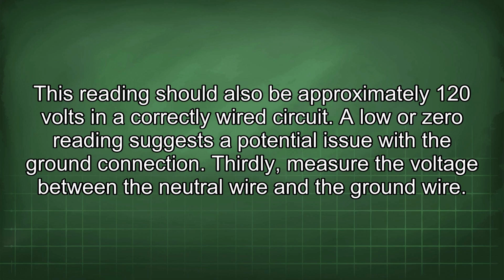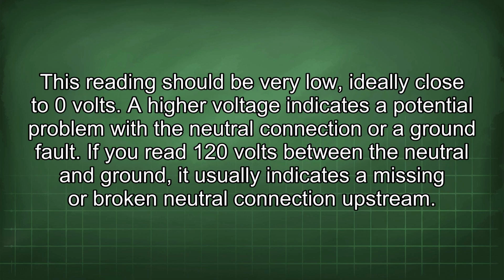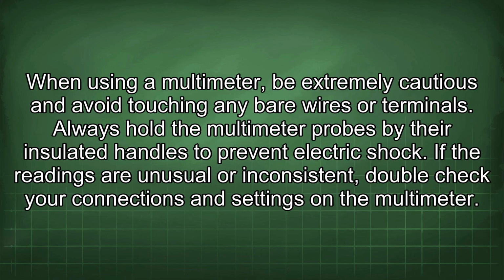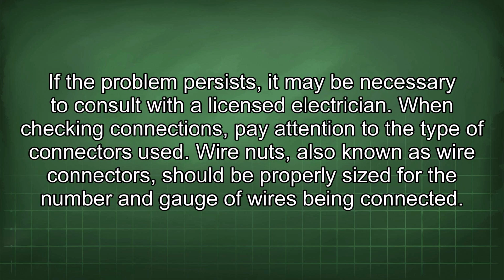Thirdly, measure the voltage between the neutral wire and the ground wire. This reading should be very low, ideally close to 0 volts. A higher voltage indicates a potential problem with the neutral connection or a ground fault. If you read 120 volts between the neutral and ground, it usually indicates a missing or broken neutral connection upstream. When using a multimeter, be extremely cautious and avoid touching any bare wires or terminals. Always hold the multimeter probes by their insulated handles to prevent electric shock. If the readings are unusual or inconsistent, double-check your connections and settings in the multimeter. If the problem persists, it may be necessary to consult with a licensed electrician.